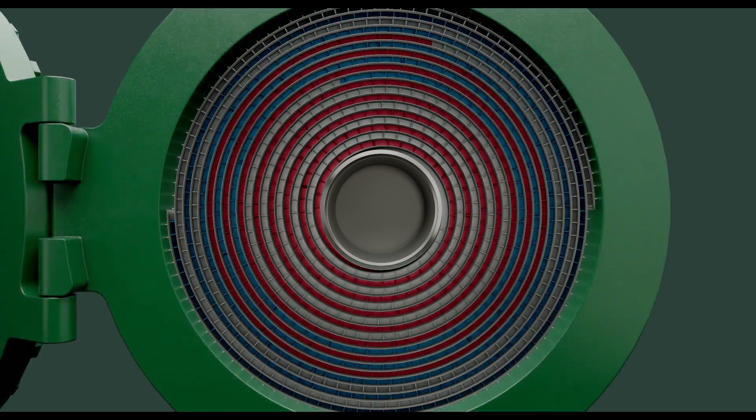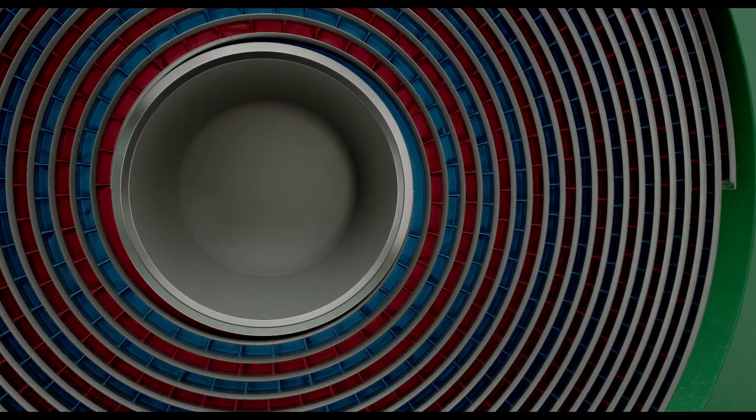They are made of two or four concentric channels with plates rolled together, with spacer pins welded to create channel gaps. Those channel gaps and spacer pins facilitate turbulent flow, customized for the customer's specific requirements and working conditions.